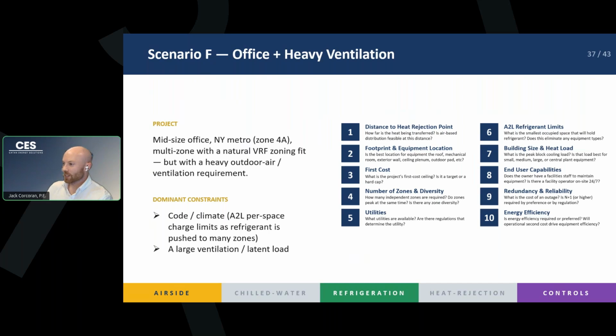And our VRF system alone cannot handle the system. So we're going to have to pair our VRF with a DOAS solution in order to get rid of that humidity before it reaches the VRF. So we're actually in this situation, which is one of our most common situations with VRF, to pair this with a DOAS system to handle latent loads, and our VRF system is going to handle our sensible loads at each zone. Together, these two systems will be extremely energy efficient. That way, your VRF focuses on what it's good at, and your DOAS focuses on what it's good at. You don't have one system that's trying to do both, and maybe is not as efficient at it.